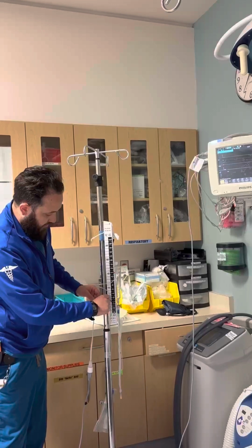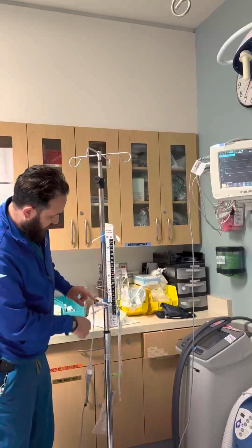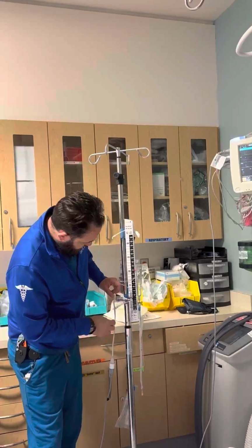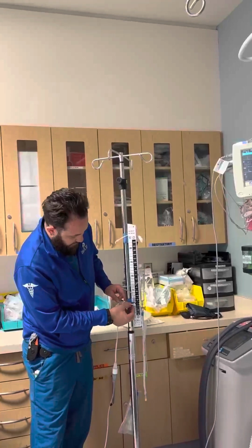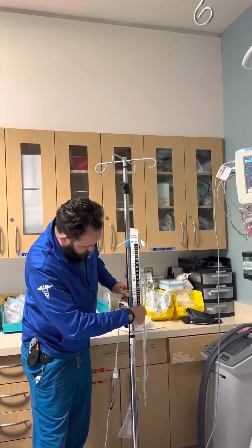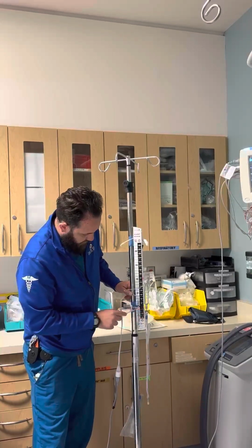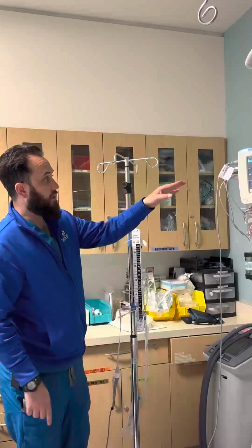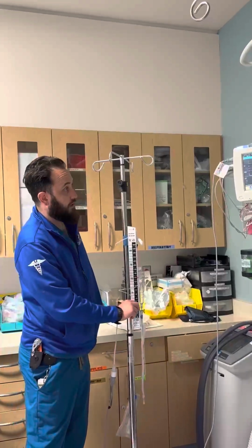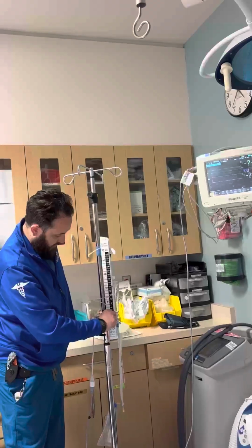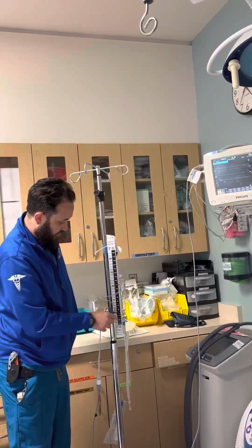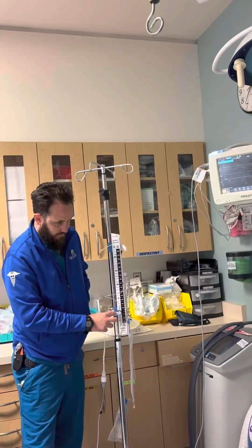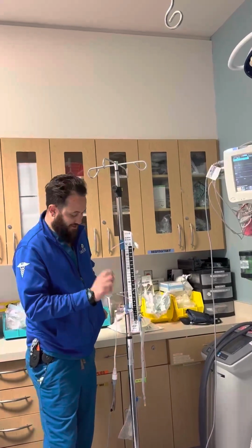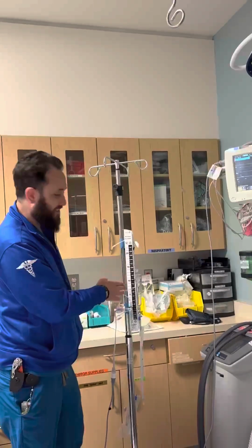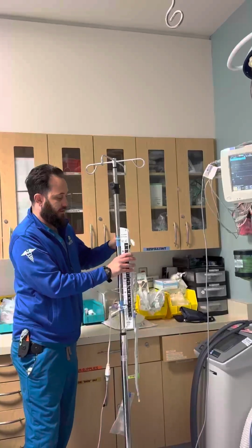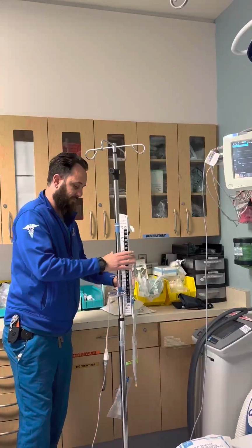Then you would, depending on if you want to read the ICP, you would open this up and then turn this off to the drain, and now you should be getting a reading. Now to drain, after you get your reading, you want to drain it to the patient. Turn it off to the transducer, and now it's going to the drain. And you can just take these rubber band things and clip them there. And that's it.